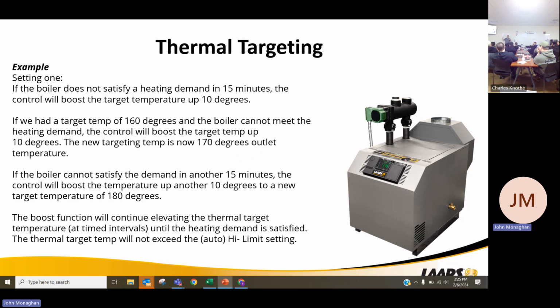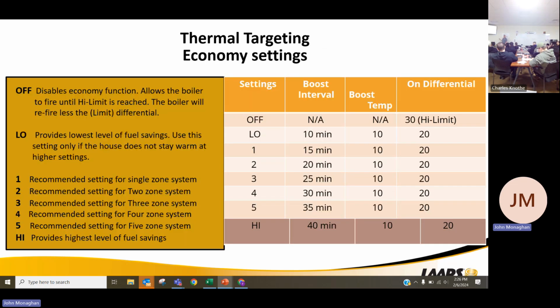So I increase my system efficiency, not my AFUE efficiency. AFUE efficiency is just that little yellow sticker that's on all of our boilers. It's kind of like the miles per gallon for cars. It's all the windows up, neutral, engine off, going downhill. Kind of the same thing with those. We're not changing our AFUE efficiencies at all, or our fuel efficiencies. We're changing how much fuel we're using and adjusting the system efficiencies. So it's looking to drive it down to its lowest temperature. This has the setback to 10 degrees.